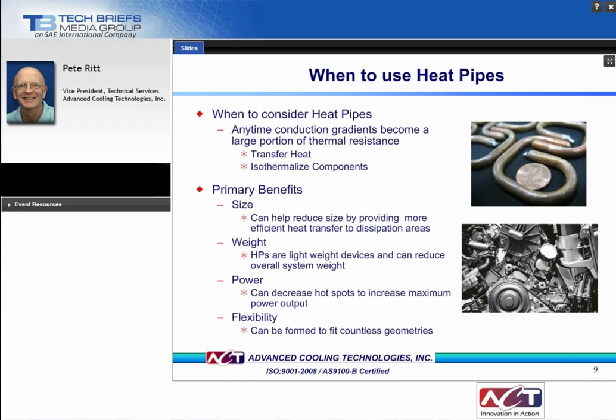In terms of benefits, heat pipes can be used to reduce the thermal management system size by providing more efficient heat transfer. It can also reduce system weight. Heat pipes are evacuated metal tubes, which are lighter than similar sized metal rods. They can reduce required power. Heat pipes themselves require no power to operate and can decrease system hotspots without need for a pump.